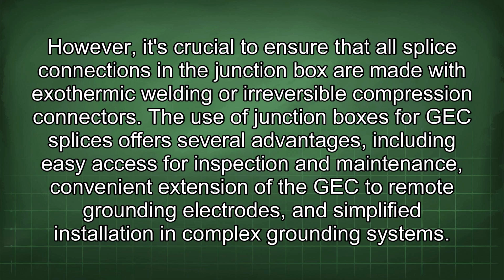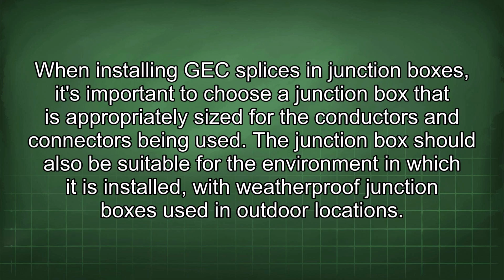compression connectors. The use of junction boxes for GEC splices offers several advantages, including easy access for inspection and maintenance, convenient extension of the GEC to remote grounding electrodes, and simplified installation in complex grounding systems. When installing GEC splices in junction boxes, it's important to choose a junction box that is appropriately sized for the conductors and connectors being used.